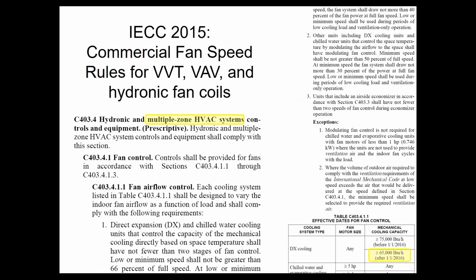The IECC is weird. The way it's worded was an error. It was worded in such a way that section 403.4.1.1, fan airflow control, was accidentally put under the hydronic and multi-zone HVAC section. So therefore, legally, it only applies to hydronic systems or multi-zone HVAC systems. That is corrected in the 2018 version. So that's no longer an issue going forward, but we're not on that version in either one of our states.